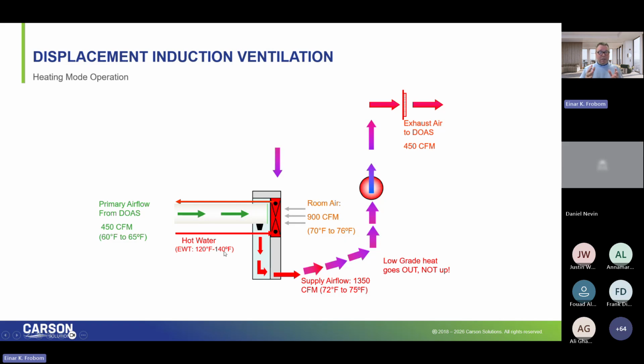If we are guiding the design teams and they have the flexibility to do so, we're typically guiding towards low grade temperature hot water. But if we do have warmer water, that's not the end of the world. I just need to know that when we're in the design. If I'm maintaining that stat at 70 degrees, all I really need is about 74, 75, 76 degree supply air temperature out of our diffuser that will stay low until it comes in contact with the students again, creating that displacement operation year round. And your market, just like ours, that's the predominant operation, 5, 6, maybe even 7 months of the year that we're in some level of heating.